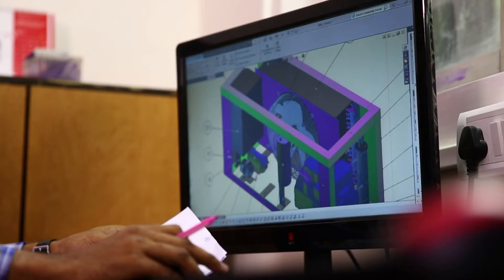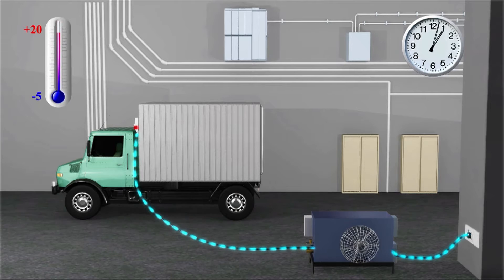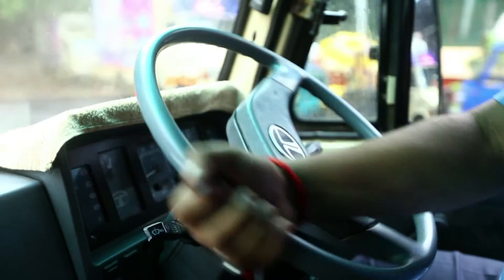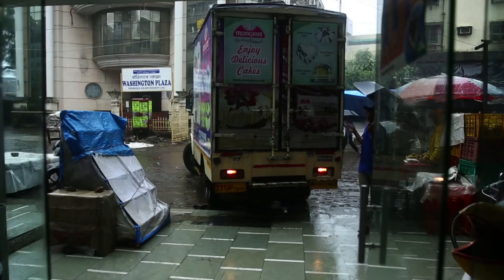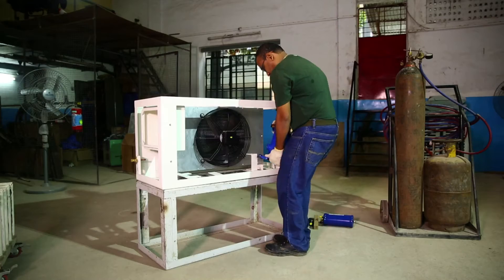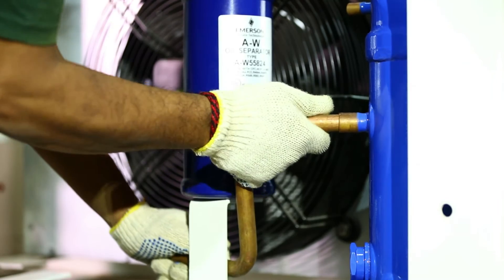Its key innovation is the heat exchanger coil and circuit design that reduces the refrigeration charging time from a typical 12 to 14 hours down to 6 hours. Once charged, the vehicle can sustain its charge for around 12 to 14 hours for multiple openings, and 20 to 25 hours for point-to-point transport. The Plug and Chill solution contains a charging unit with a compressor and condenser for the refrigeration system, an automatic controller, and an electrical fan.